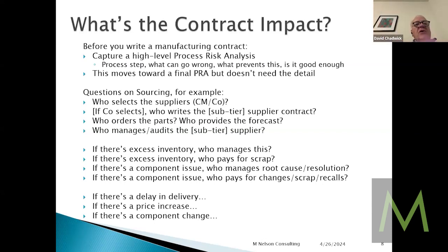Each manufacturer shall establish and maintain requirements, including quality requirements, to be met by the contractors and consultants. And then if you read 820.50, it runs through everything like that. As the manufacturer, as the one putting the product on the market medically, we are the responsible party. We're responsible for our subcontractors. I would say we become responsible for subs because we're looking at the manufacturer of the component and they have specifications. And if they start making it incorrectly or dimensionally, or the bottles are higher than they used to be, that causes medical problems for us under the quality system. So I want to be sure that we're not mixing up buying something for a non-medical product versus a medical product, because we have QSR to deal with.